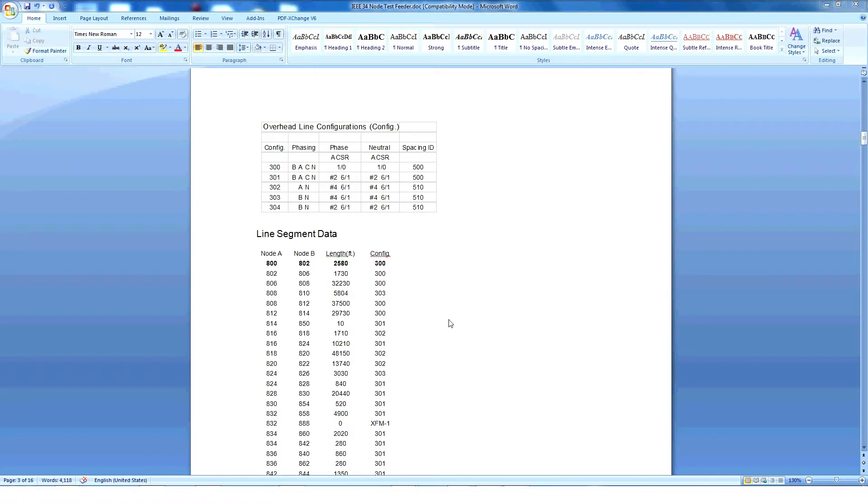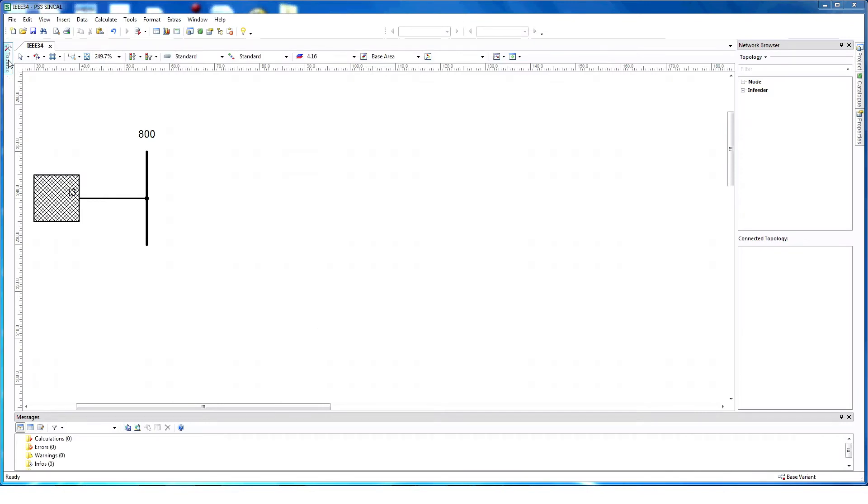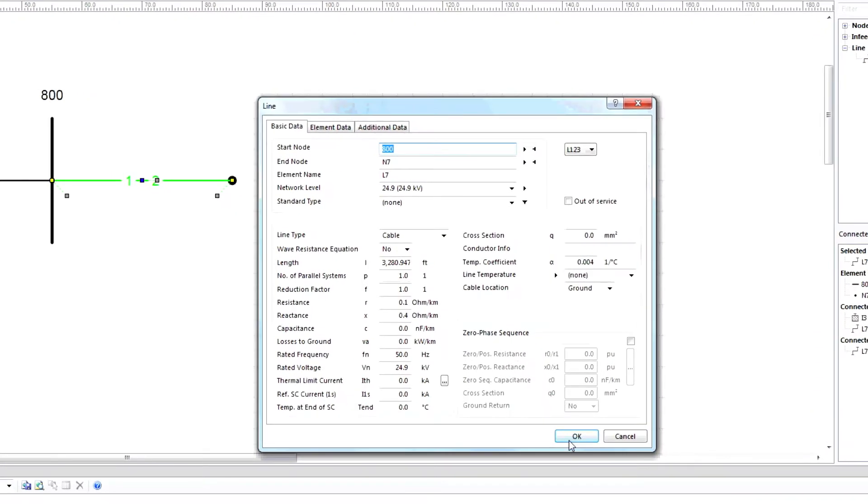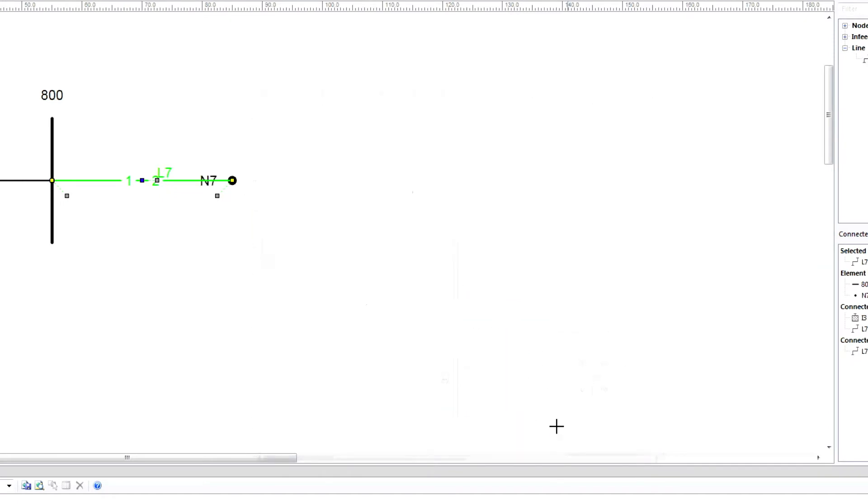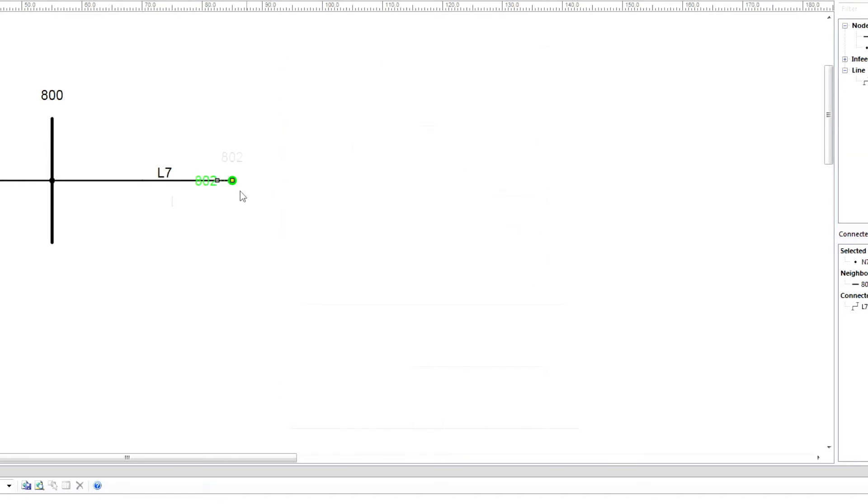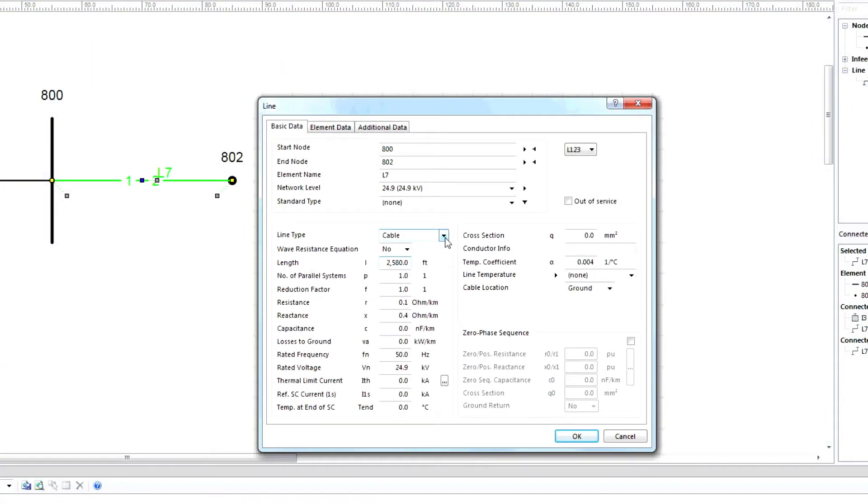Now create a line. An example is provided from node 800 to 802, length 2580 feet, and configuration 300. Line configuration has Z and B in a matrix format. This information is needed to create a line model in PSS SynCal. To create a line from the toolbox, select Line and click OK. Choose a node name, select the correct voltage level and click OK. Now we need to enter the line parameter information. We can see for node 800 to 802 the length is 2580 feet.